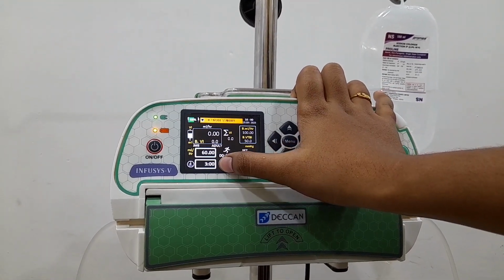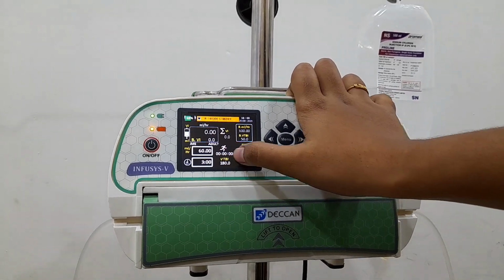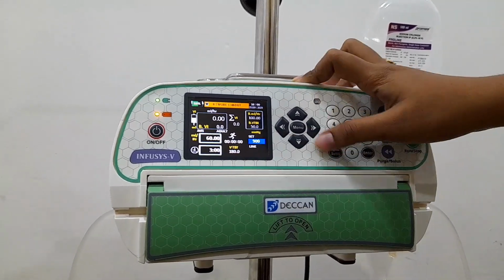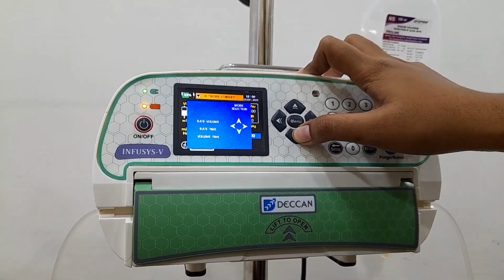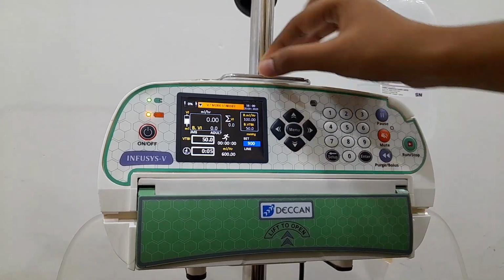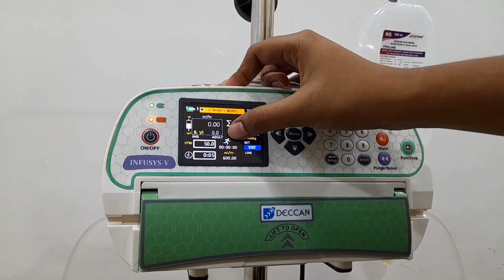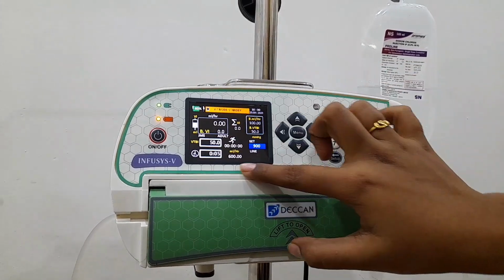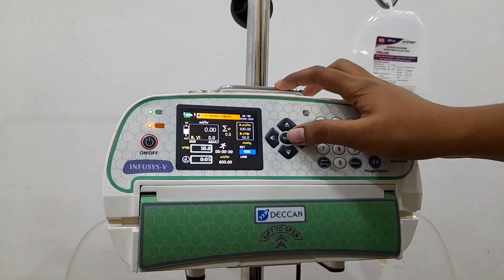Here we can set rate and time. Based on that, VTBI will be calculated. And we move to another mode, volume time. Whenever we change the mode, the status bar displays the same. Here we can set the volume to be infused, and based on the time, the ml per hour will be calculated.